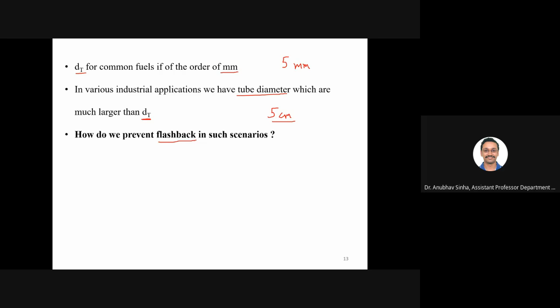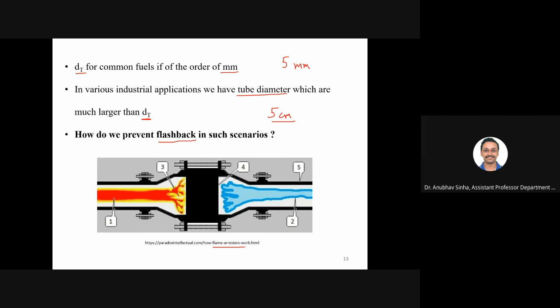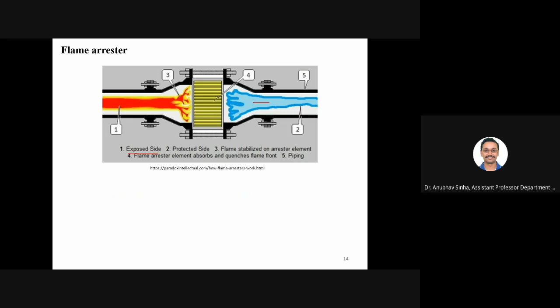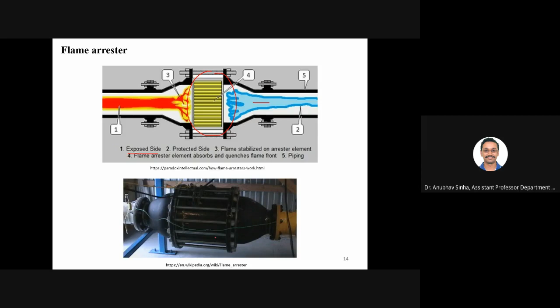Generally we don't only cool the tube, we basically cool the whole flame. So what you're looking at is called a flame arrestor. One side is the exposed side where we have the flame, and the other side is where you don't want the flame to go. Now we have a flame arrestor in between, which looks like this. This is from an industrial application. Its purpose is that it will extract the heat from the flame. What you say about a cooler tube is also a good idea, but the tube is large, so just cooling at the wall will not work. So I will cool the flame throughout by using something like this. This is some wire mesh.